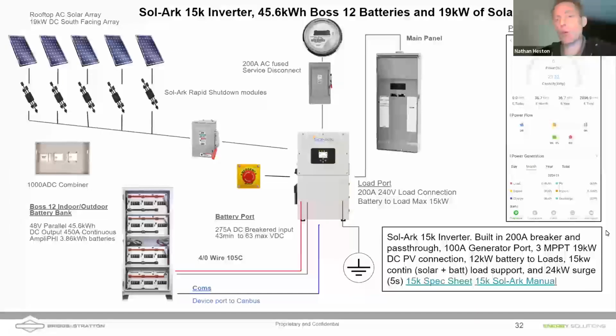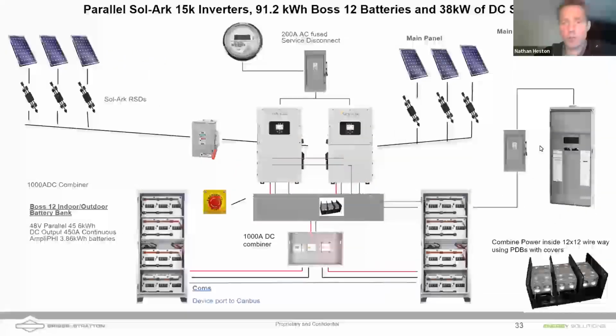So coming back to our wiring diagrams, now that we've seen all those connections, this is what it looks like when we're putting our system together. And I've got this here in case you want to run back through with questions. But the communications port, like I said, you're running 1 wire from your communicating battery over to that inverter. And then if you've got a single home run of 4-aught, you might want to use those combiner bars.